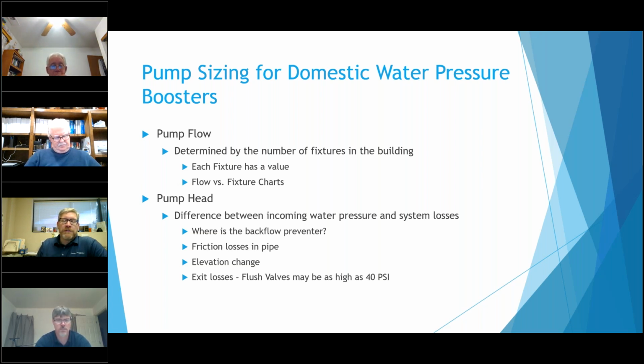So first thing I would always ask is, where's that backflow preventer? A lot of times those are somewhere between a 10 and 20 pound drop across them. So someone might say, well, I got 40 pounds coming in, I need 80 going out, and that's fine. But if that backflow is before the package, you don't exactly have 40 pounds coming in, it's lower. So you may have to worry about how low that pressure the pump can go down to.